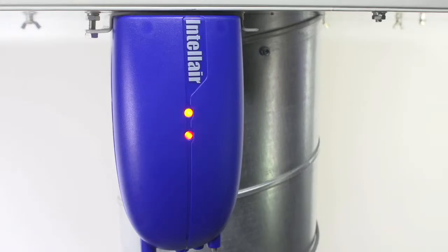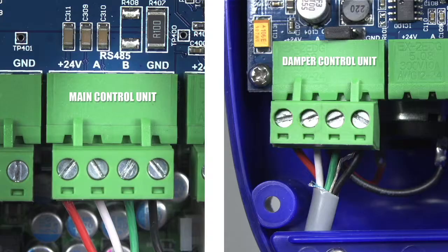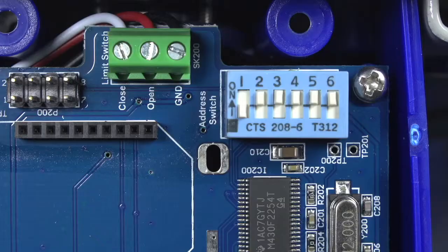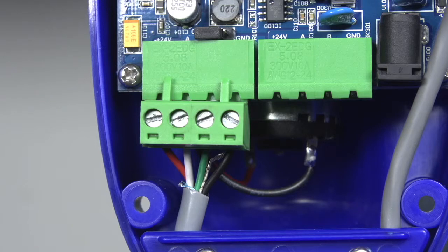If all of the damper control units are not discovered, firstly, check the physical cabling connections and then check the DIP address doesn't clash with any other device. If power LEDs are not displayed on DCUs, check cabling connections.